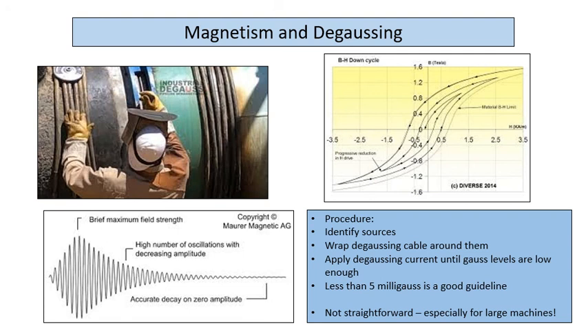Often you have to disassemble the component, especially with bearings. So the correct procedure is to split up your machine into individual components and demagnetize them individually. So it can be complicated, but it can often be the only way that you'll resolve a serious shaft current issue.